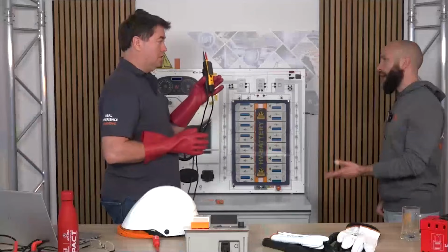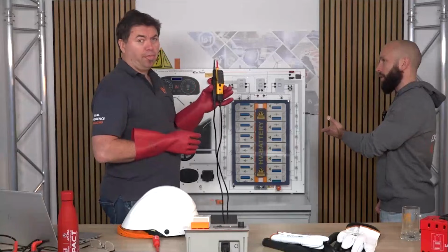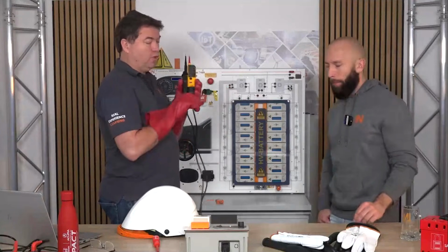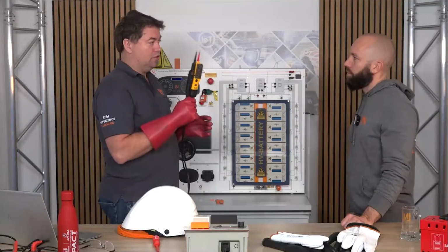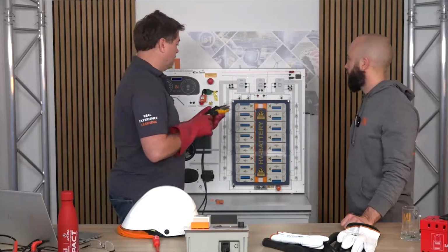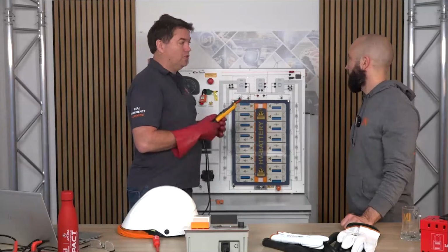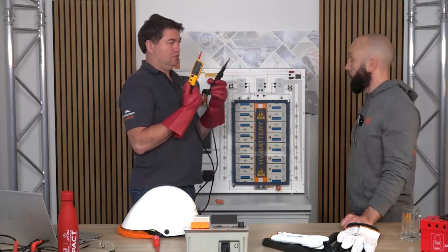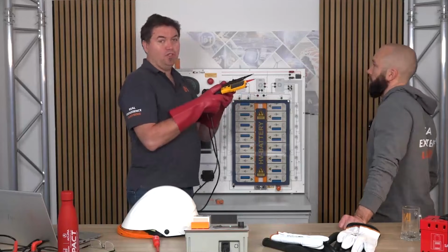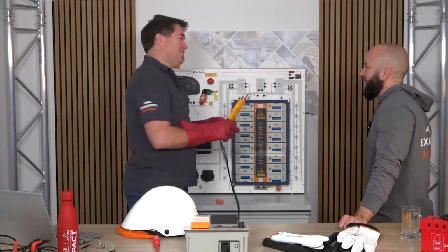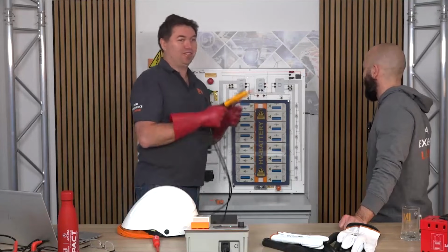This is important to do at DC, as the dead measurement is at the DC source. What I just did is make sure the tester works - there's no point going to the high voltage point and finding this is broken. If you come up and think there's no voltage there, start working on it, and then get zapped.